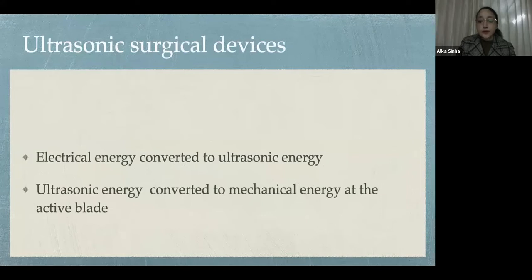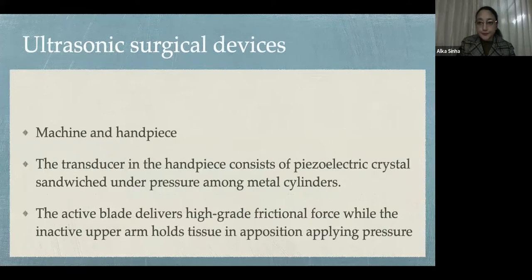Coming to the topic for today, ultrasonic surgical devices. How do they work? Basically, electrical energy is converted into ultrasonic energy, and this is delivered as mechanical energy at the active blade. There's a machine and a handpiece. The transducer in the handpiece consists of piezoelectric crystals, which generate the ultrasonic vibrations. This is delivered as a high-grade frictional force at the active blade, while the other blade, the inactive blade, holds the tissue in position, applying pressure. This is the basic principle of all the ultrasonic shears which are available.